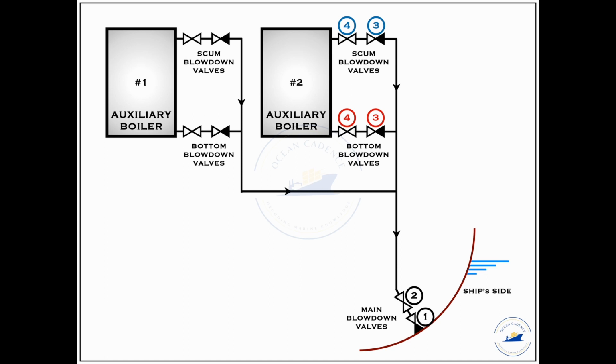And once we have done that and charged the fresh batch of water, we should allow the circulation of water and the entire steam generation process to occur for a certain amount of time, let's say a batch of 12 to 24 hours, before we carry out the next test to gauge the condition of the boiler feed water as well as the circulation water inside the system.